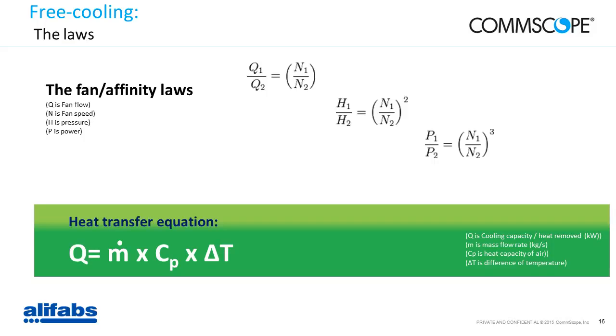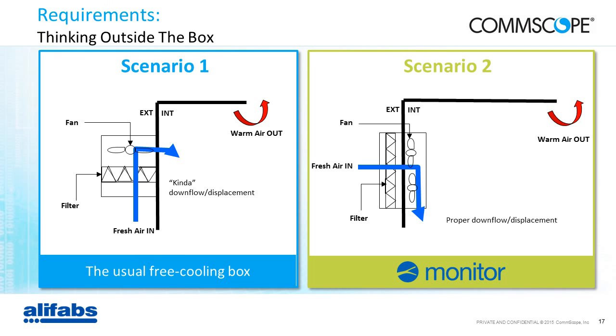Now, these are just scientific laws that everybody uses in the industry. I'm going to take you through what makes us so different. So just thinking outside the box, you probably know many free cooling boxes. And you can see on the picture, on scenario 1 on the left side, this is how it usually works. It draws fresh air in, goes through the filters, and just blows in. Very often, you have little grills that direct the air towards the bottom of the site, and there is a natural air displacement, sort of breaking the thermal stratification in the shelter, with the warm air being dissipated usually at the opposite side of the shelter.